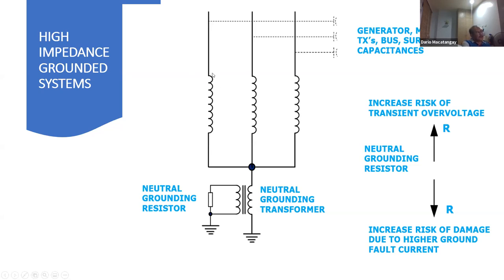If you have a fault at the terminal, what you see is a full line to neutral voltage here. Let's say your generator is rated at 13,800 volts line to line. If you divide that by the square root of 3, the line to neutral voltage rating is 7,968 volts. During normal condition, this voltage is almost zero, so the voltage from this point up to this point is 7,968. If this is phase A, this is 7,968 at angle zero.